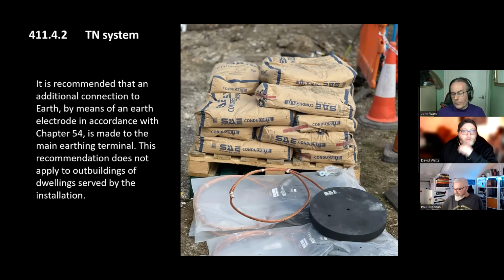Yeah, this is a thing that they've tried to put in before in several previous drafts. Just to be clear here, we're talking about a TN system, so this is not a TT thing where you're putting in the electrodes. This is a TN, so it's TN-C-S in most cases, or possibly TN-S. The point of this is to put one in so that in the event of certain types of fault on the network, it will keep the voltage on the exposed parts down to a sensible level. Now, it says it's recommended, which you could take to mean, well, we can't be bothered, but in reality, recommended means you should be putting it in. And this is just putting an electrode in, connecting it to the earthing terminal.